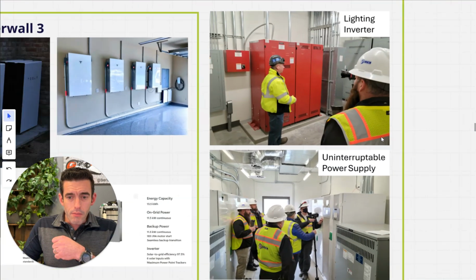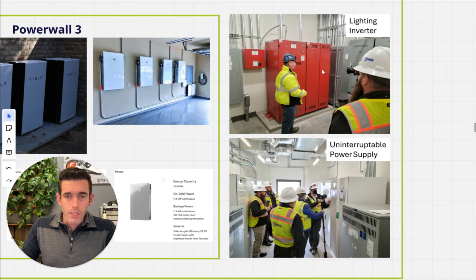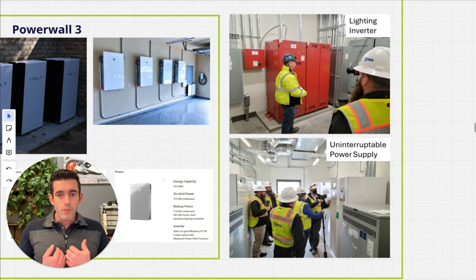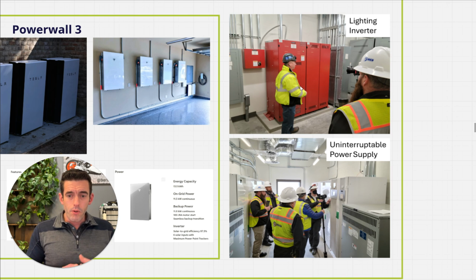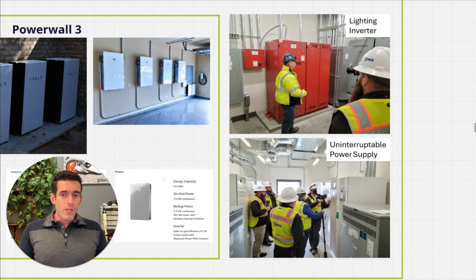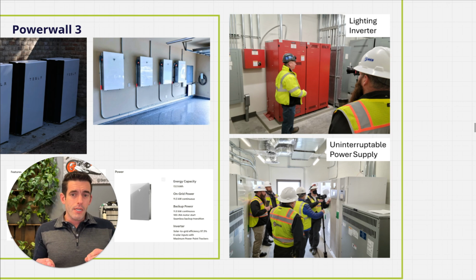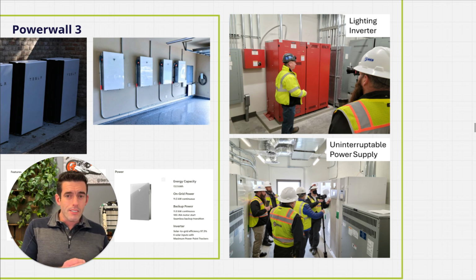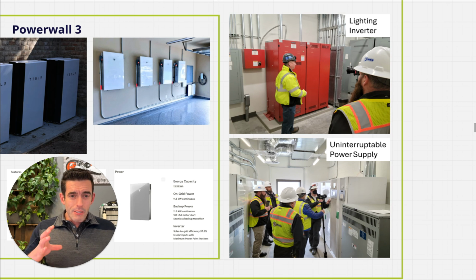In a commercial building, these two things are the same exact device, both from my projects in my prior role. The white one is a UPS supporting IT loads. The red one is a lighting inverter, also a UPS, supporting emergency loads. The code required two separate things. They're both batteries, and if this equipment had been able to provide power directly to the lights as DC voltage, you wouldn't need these big power blocks, these big inverters in place.